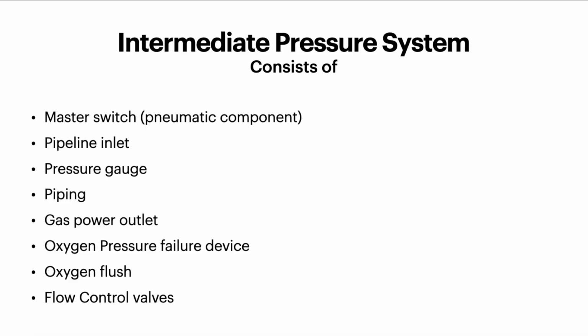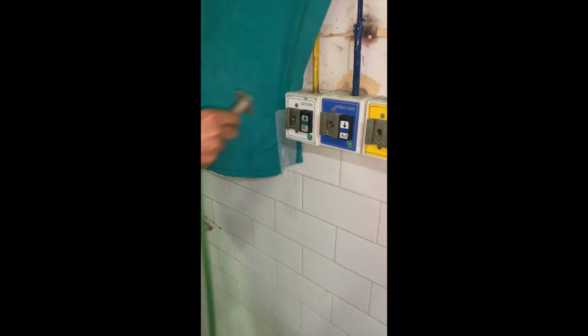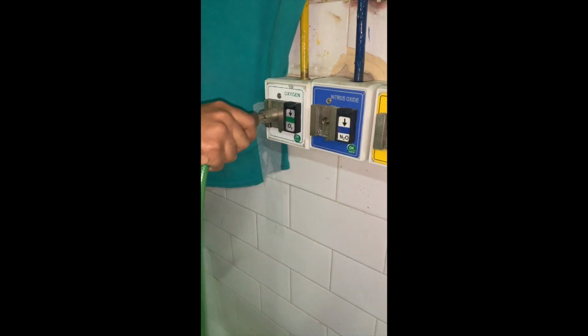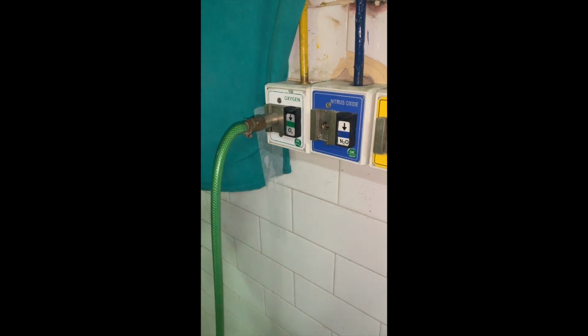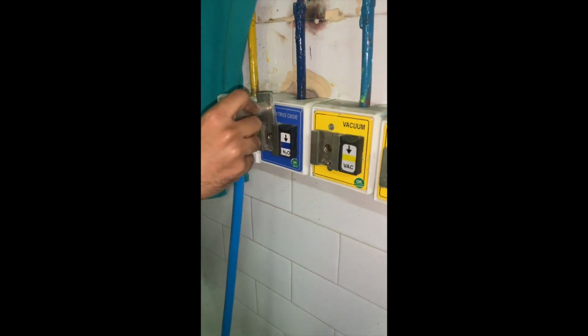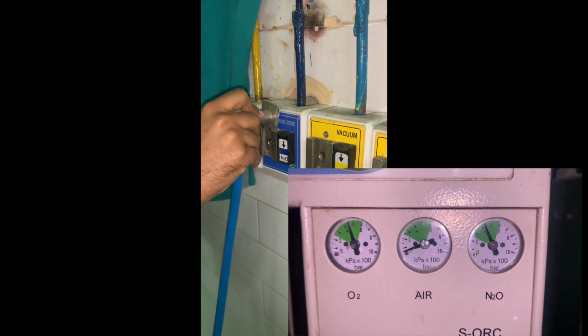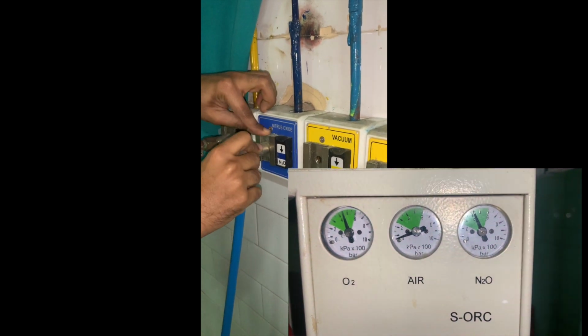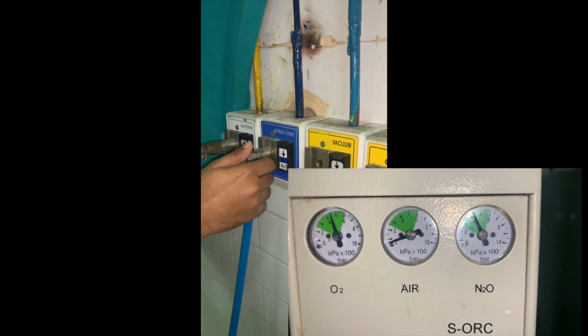The intermediate pressure system consists of the master switch, pipeline inlet, pressure gauge, piping, gas power outlet, oxygen pressure failure safety device, oxygen flush and flow control valves. Check for the connection of the pipeline to the supply outlet via a tug test and look for pressure in the pressure gauge. The pressure should be at least 50 psig or 345 kilopascals.